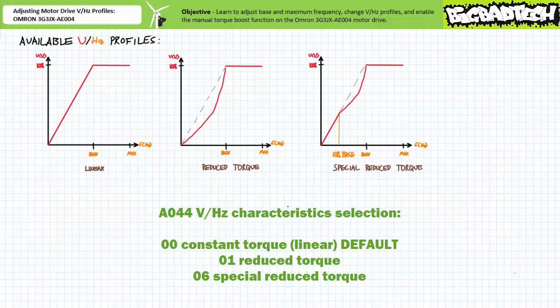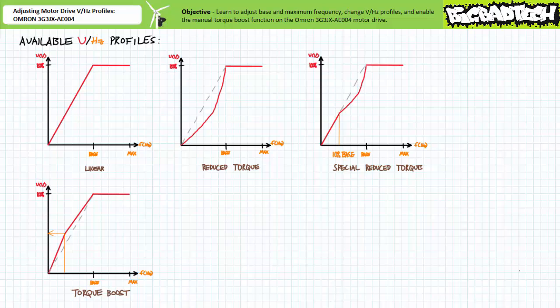To change among the available volts per hertz profiles, an operator needs to change extended function parameter A044. The volts per hertz characteristic selection has three available options: 00, the default, is constant torque — a linear volts per hertz ratio; 01 is a reduced torque profile; and 06 is a special reduced torque function. The fourth volts per hertz profile is a user customizable modification of the linear volts per hertz profile called the manual torque boost function, which allows an operator to manually select a steeper initial applied voltage slope at lower excitation frequencies for the purposes of establishing an initial burst of current at low speeds.